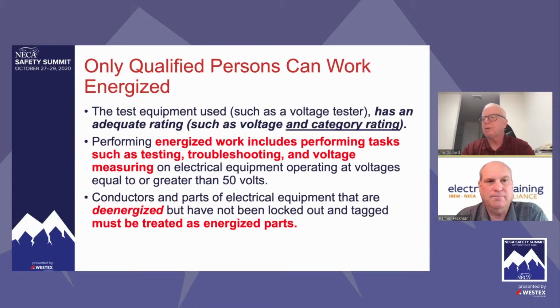Yeah, Palmer, and that's a good point. I'm glad you had me go back, because even today we see the lack of lockout tagout. We see devices opened, and in many cases they put a piece of tape across it. And when I would walk through a job and see a guy working in a panel board terminating branch circuit conductors, I saw a feeder landed into it, I would ask them, is this in an electrically safe work condition? And in every case they would say yes. And then I would say, well, then you won't mind grabbing the bus. And I can tell you, nobody ever grabbed the bus.